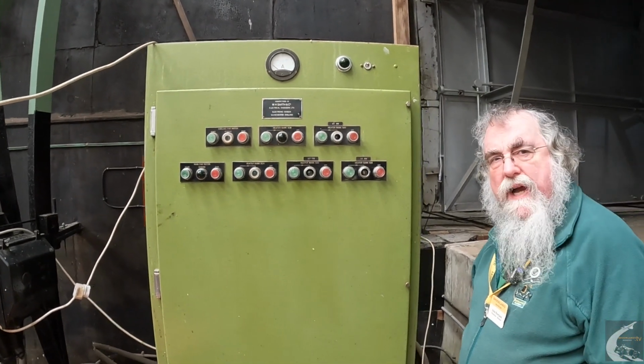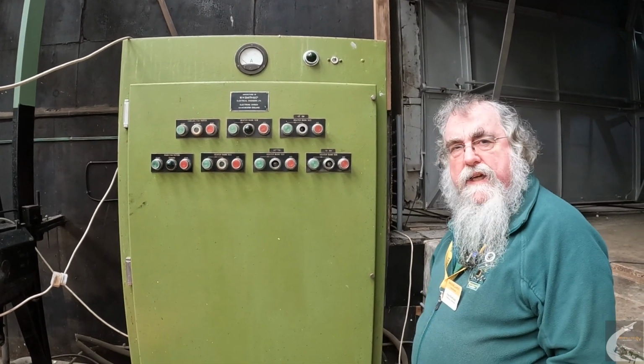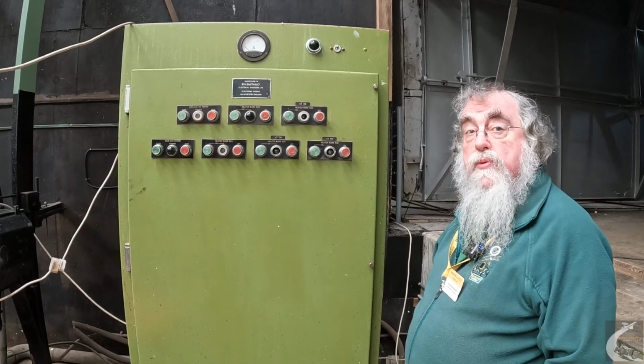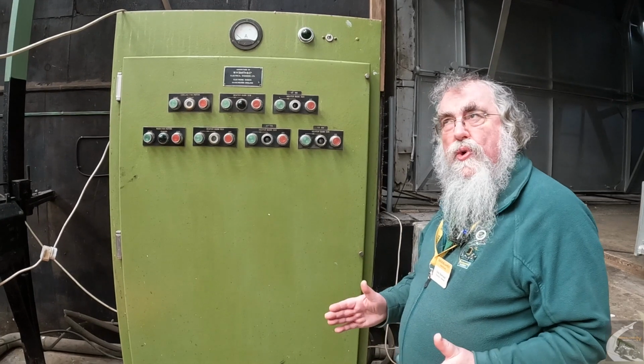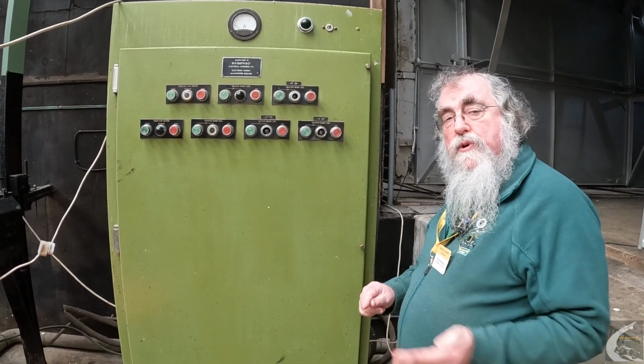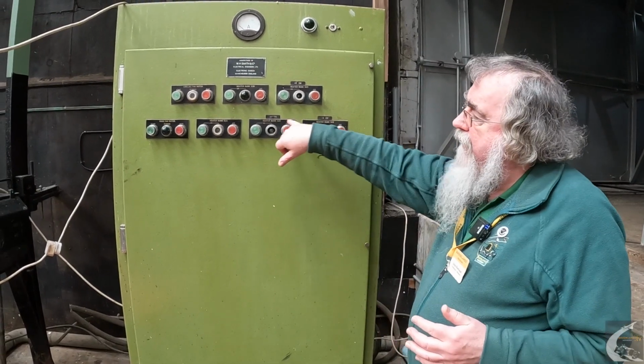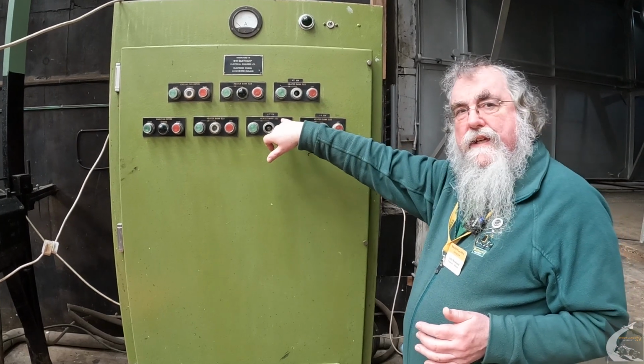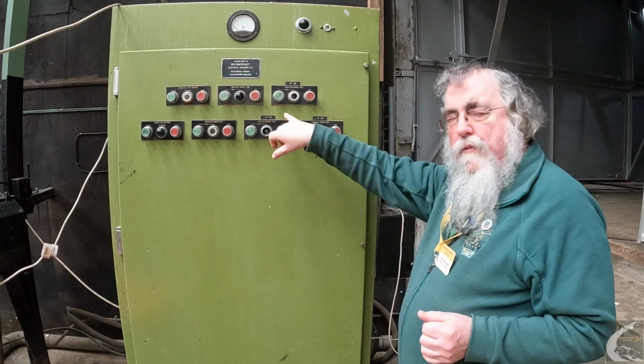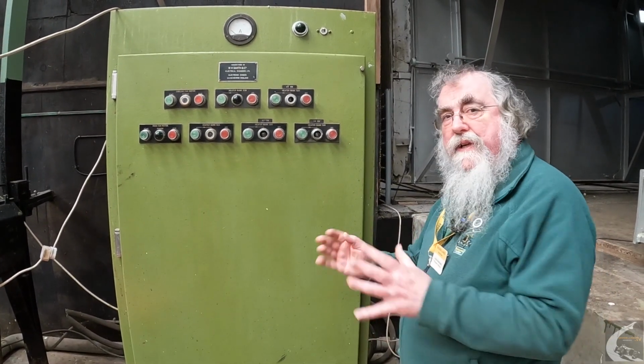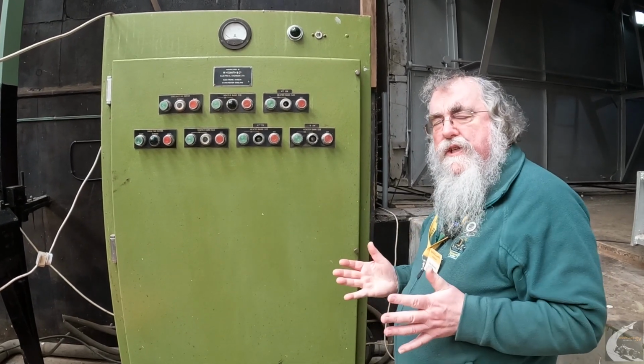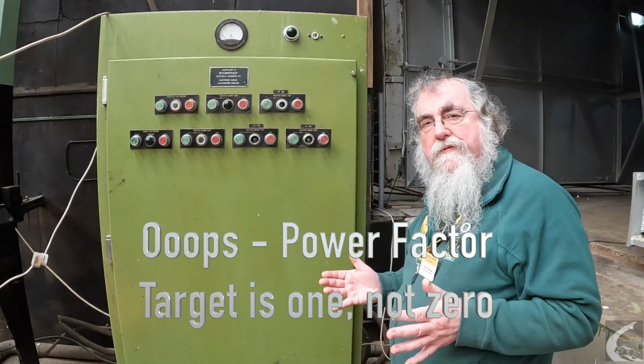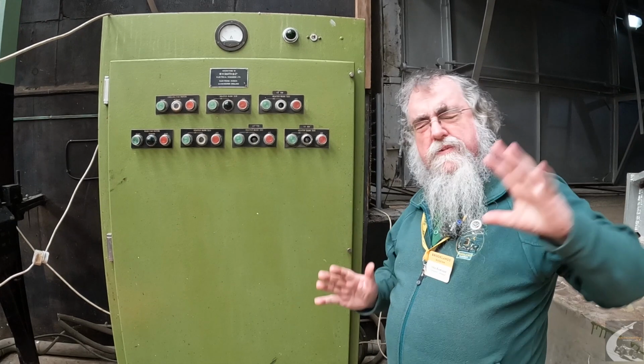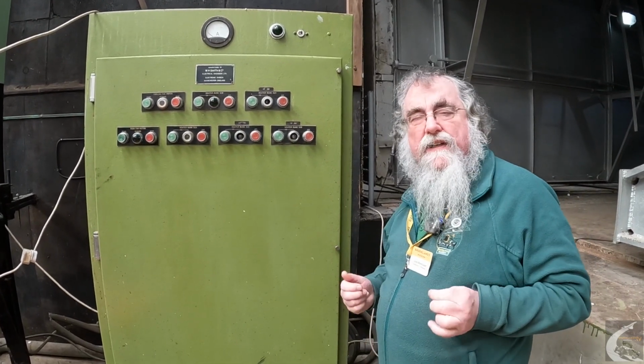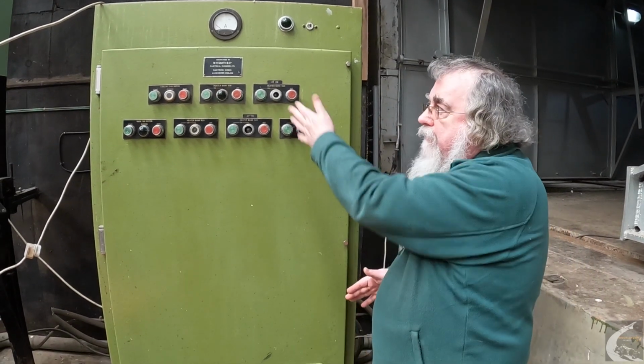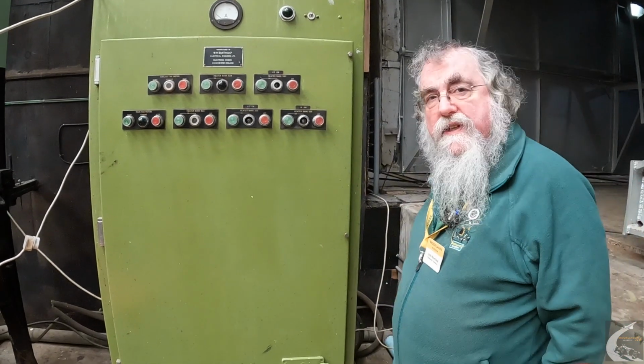When you're measuring power on an AC system, you would measure it as being kilovolt amps. So that's volts times amps normally equals watts. But in an AC environment, you're not quite sure what the power factor is, so you may not get all of the power you're putting in coming out as useful energy. Now here, these are the ratings of the heaters, so that's actually what the heaters would generate in actual watts. How much kVA we put in would probably be greater than that, depending on the power factor, as I say. We always try to get a power factor of 1, but very rarely achieve that on anything that's inductive. So anyway, upstairs you may have noted it refers to kVA, which is the nearest thing we have to power. Whereas here it does talk about watts, because that's actually the heating system underneath.